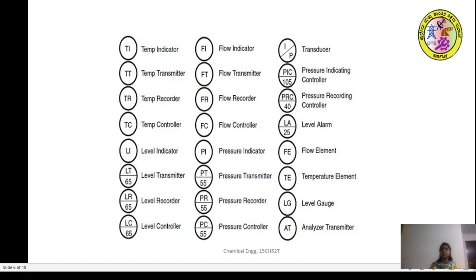indicator; PT is a pressure transmitter; PI is a pressure indicator; FC is flow controller; FR is flow recorder; FT is the flow transmitter; FI is the flow indicator. Or transducer, this is very important: I/P is a transducer. PIC is a pressure indicating controller, these you have to remember. PRC is nothing but pressure recording controller. So the first letter of each word may be used as nomenclature for that particular element in a process.